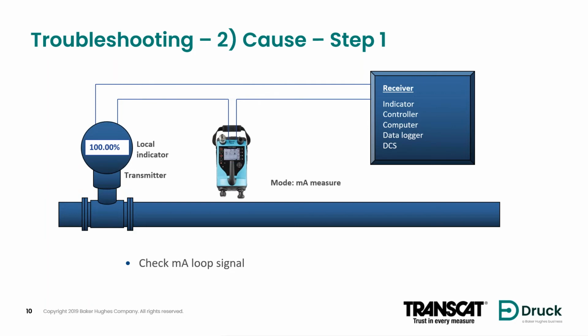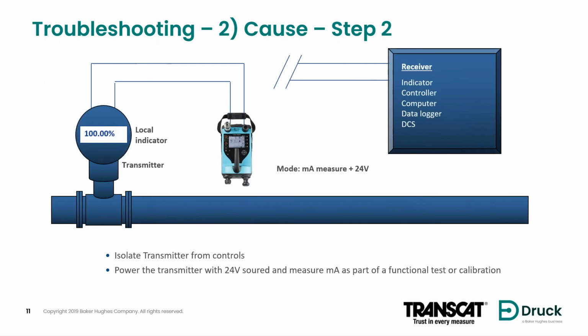So we could perform that test with the built-in loop generation capability function. It's probably energized, so we would just use the milliamp or current measure capability on the calibrator for this particular step of troubleshooting. The next step would be isolating the transmitter itself from the controls. Again, with the portable pressure calibrator, we can generate a pressure to the transmitter and measure the output. So isolating the transmitter, we can power the transmitter with a 24-volt source, again available in the calibrator, and measure the 4 to 20 milliamp current off of the device.